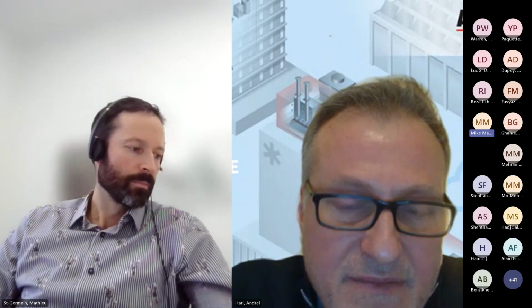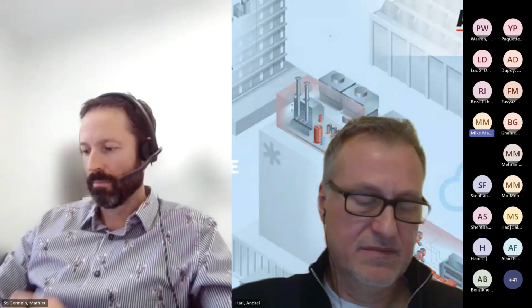Andrei, thanks for that great presentation. I learned a lot from it. The question is on the last topic you covered, with respect to redundancy. For our project, we would have traditionally sized 2 pumps at 30 horsepower each, and using your methodology or approach, we decided to size 2 pumps at 20 horsepower each. Facility owners are very wary of situations which probably will never happen but can happen, and that is that we lose 1 pump on a design day.